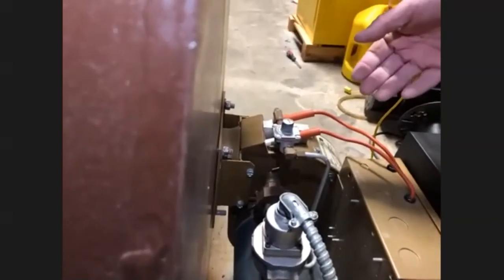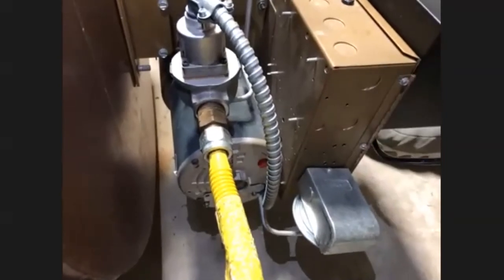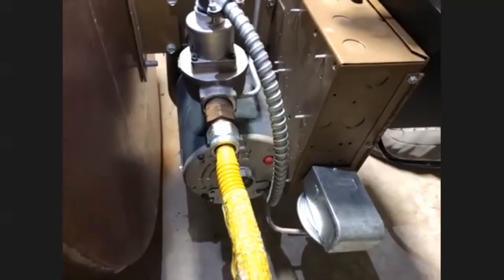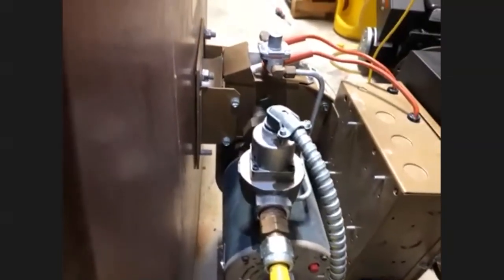I'll come around and show that here. See this air tube right here coming out of the air proving switch. And that goes into the fan housing. That's verifying that there's pressure coming from the fan blower. It's triggering that switch, and that triggers inside the ignition component to let it know there is air pressure. If the blower stops running, chances are this air proving switch was not reading the proper pressure and it did not trigger. So it's a safety precaution.